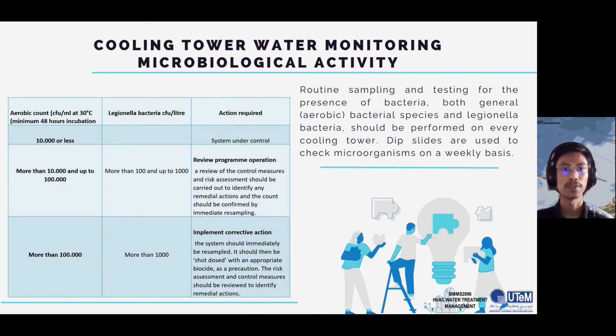Okay, for cooling water monitoring of microbiological activity, routine sampling and testing for the presence of bacteria, both general bacterial species and Legionella bacteria, should be performed on every cooling tower. Dip slides are used to check microorganisms on a weekly basis. Okay, showing on the table, there are several types of methods used to control Legionella bacteria and its effect on the environment.